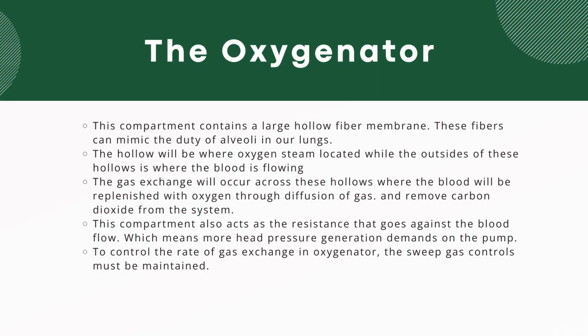So the next part is the oxygenator. This compartment contains a large hollow fiber membrane. This fiber can mimic the duty of alveoli in our lung as a gas exchange. The hollow space is where the oxygen stream is located, while the outside of this hollow is where the blood is flowing. Once the blood is completely flowing through, the oxygenator will have these membrane layers wrapped across the entire body. The gas exchange will occur across this hollow, where the blood will be replenished with oxygen through diffusion of gas and carbon dioxide is removed from the system.